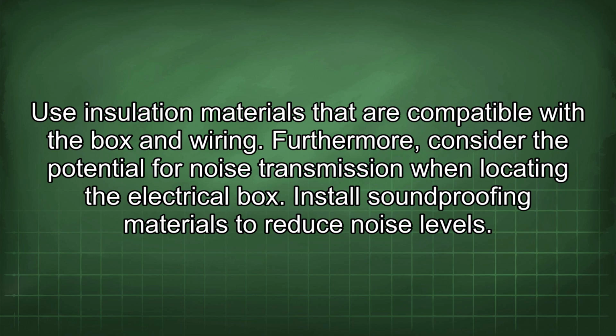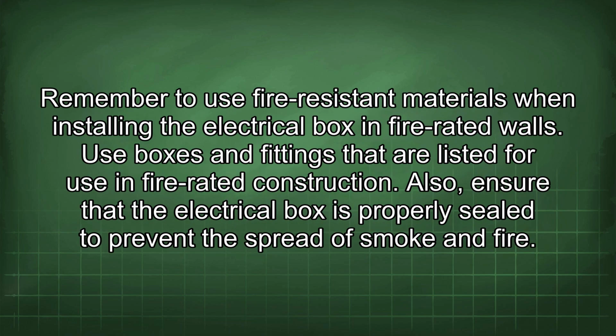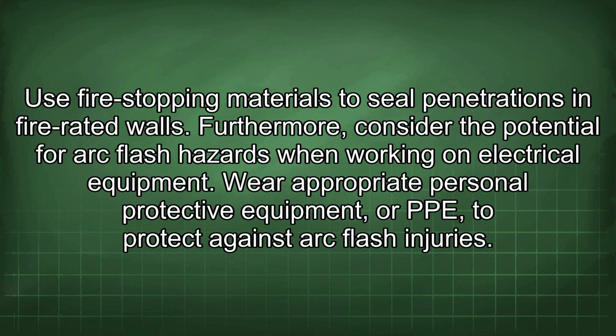Furthermore, consider the potential for noise transmission when locating the electrical box. Install soundproofing materials to reduce noise levels. Remember to use fire-resistant materials when installing the electrical box in fire-rated walls. Use boxes and fittings that are listed for use in fire-rated construction. Also, ensure that the electrical box is properly sealed to prevent the spread of smoke and fire. Use fire-stopping materials to seal penetrations in fire-rated walls.